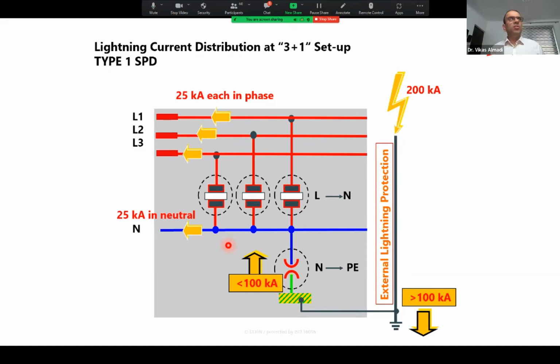How are the SPDs installed? SPDs are installed like this, in parallel to the equipment, this side is the equipment, and line to neutral, each line to neutral, there are 3 SPDs, and 1 SPD is between neutral and earth. So all are spark gaps, there is no leakage here from line, neutral to earth. So no possibility of aging and no damage, mechanical devices, no problem of voltages and all.